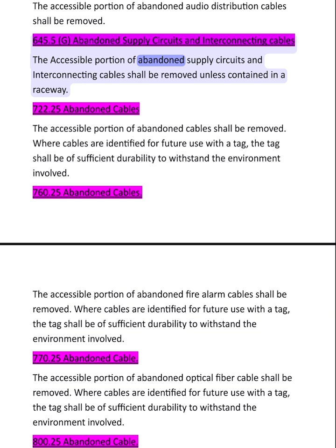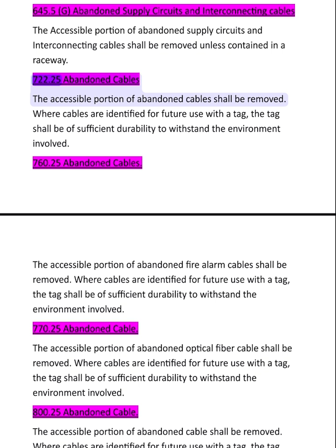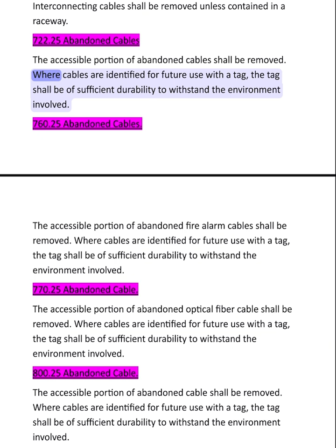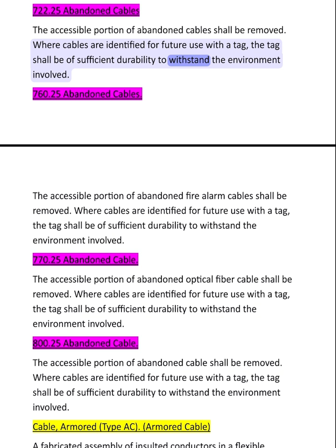645.5(G) Abandoned supply circuits and interconnecting cables. The accessible portion of abandoned supply circuits and interconnecting cables shall be removed unless contained in a raceway. 722.25 Abandoned cables. The accessible portion of abandoned cables shall be removed. Where cables are identified for future use with a tag, The tag shall be of sufficient durability to withstand the environment involved.